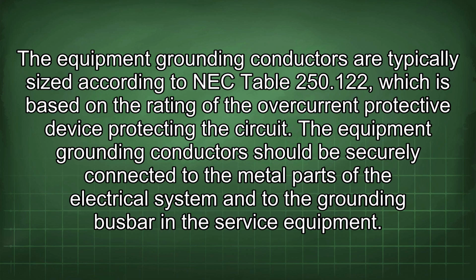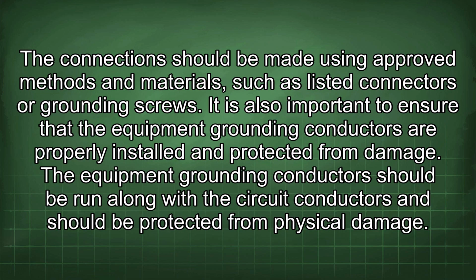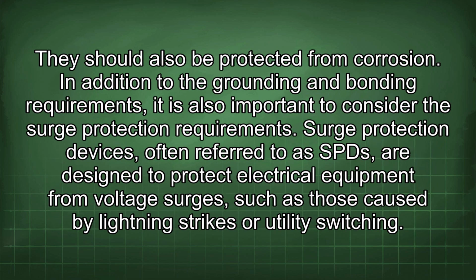The equipment grounding conductors should be securely connected to the metal parts of the electrical system and to the grounding busbar in the service equipment. The connections should be made using approved methods and materials, such as listed connectors or grounding screws. It is also important to ensure that the equipment grounding conductors are properly installed and protected from damage. They should be run along with the circuit conductors and should be protected from physical damage. They should also be protected from corrosion.